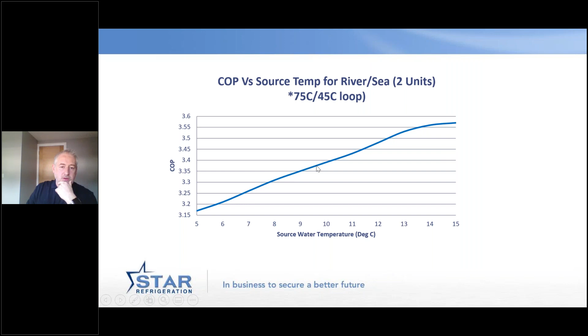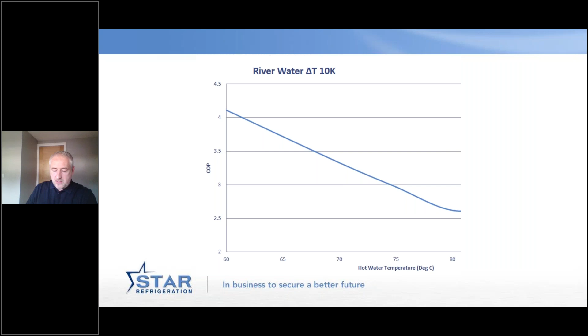Equally though, on the hot side, if instead of feeding out at 80 degrees, we can feed at 70 degrees, you can see we're changing the COP from about 2.6-ish up to about 3.4-ish. And that's a massive difference in value. So it's about helping the system operate at its absolute peak, and having the equipment there. If we hadn't installed a subcooler and the ability to flex the condensing temperature, we wouldn't be able to offer these ongoing benefits.